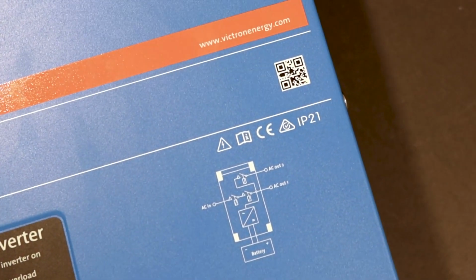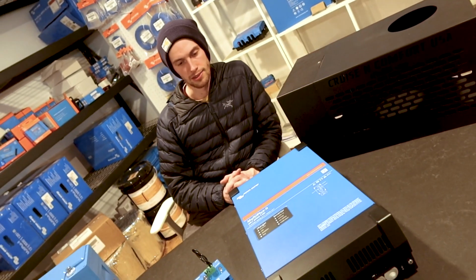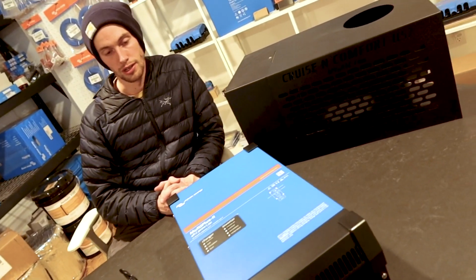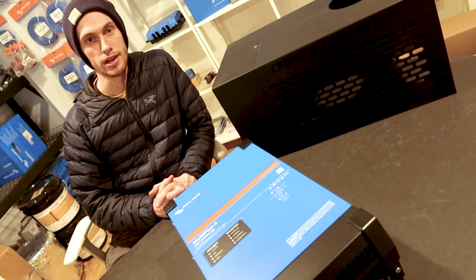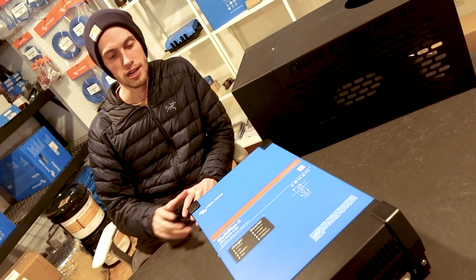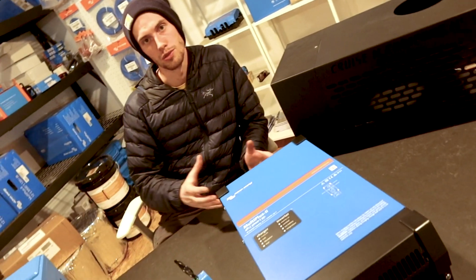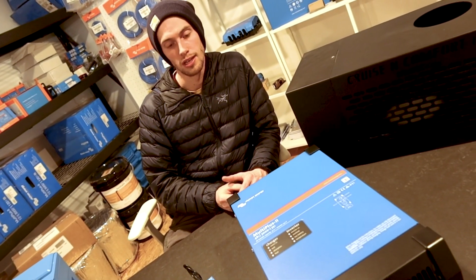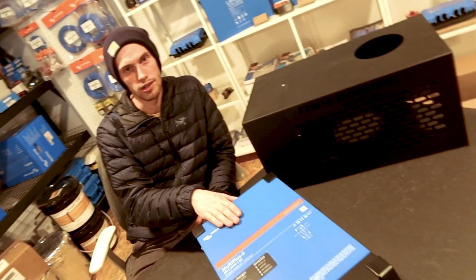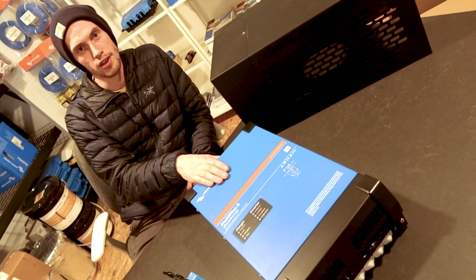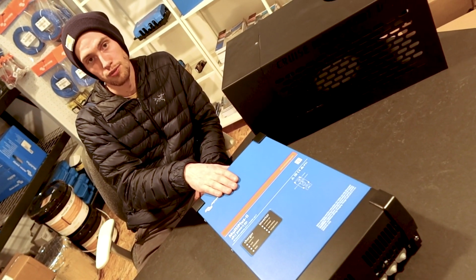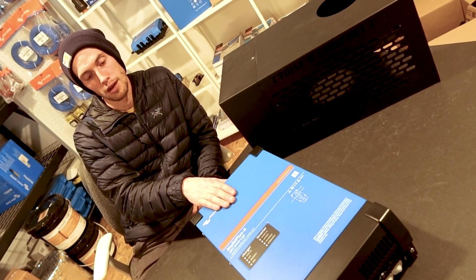It's really important that Victron Multipluses, and their inverter and inverter charger series, are all rated in VA ratings — which reflects the energy coming out of the batteries, not the continuous usage on the other side. We see that a lot. This is not a 3000 watt inverter, it's a 3000 VA rating, which gives you 2400 watts continuous on the output side.